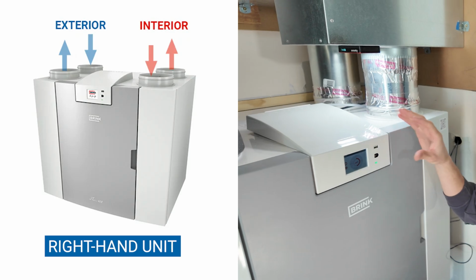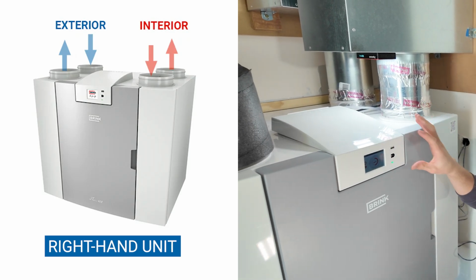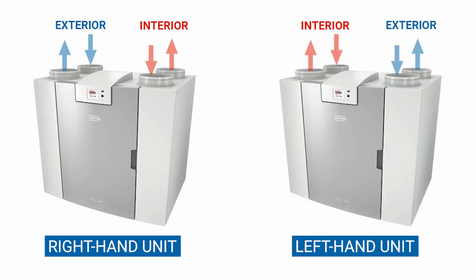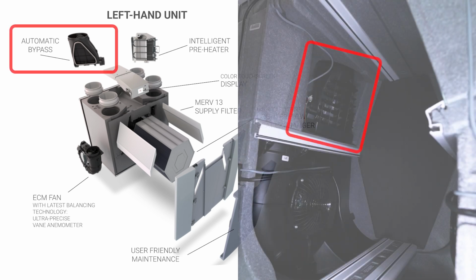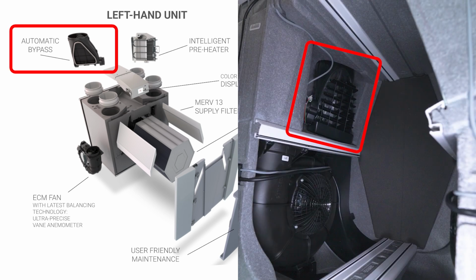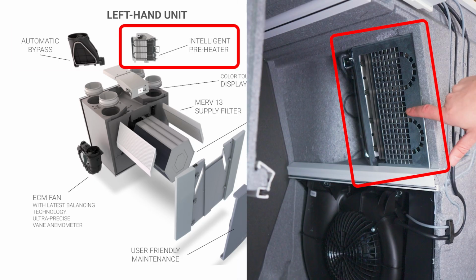If it is a right-hand unit, which this site has, the home side duct connections are on the right when facing the unit. The supply manifold should be connected to the back right port. The extract manifold should be connected to the front right port. For left-hand units, conversely, home side ducts are on the left, with back left as extract and front left as supply. You can also verify where the home side extract port is by locating the bypass valve. The fresh air intake can be confirmed by finding the preheater.